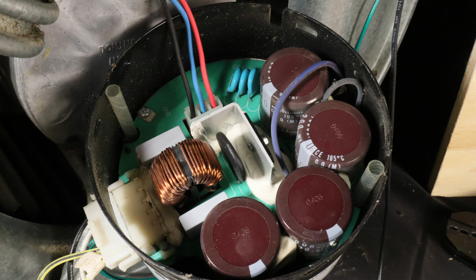So when the motor first starts up, it's going to want to pull this big inrush of current in, and this thermistor prevents that with that high resistance. But once it warms up, the resistance drops, and the motor can pull whatever current it needs. So this is kind of like protection. Now, these thermistors are a very common fail point, and you can test them by ohming them out.